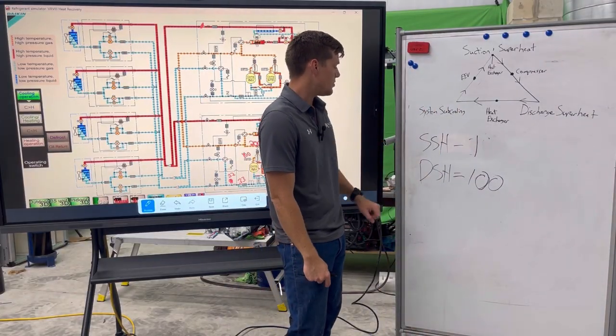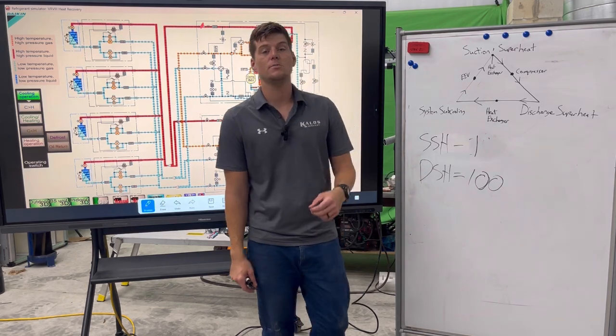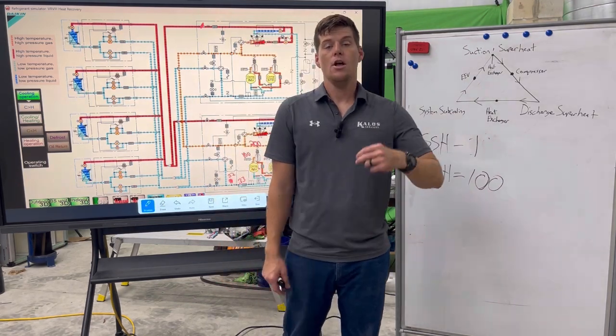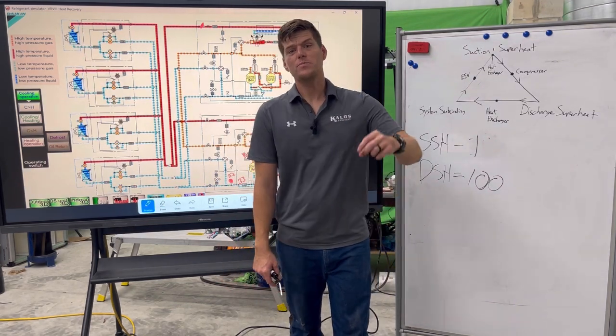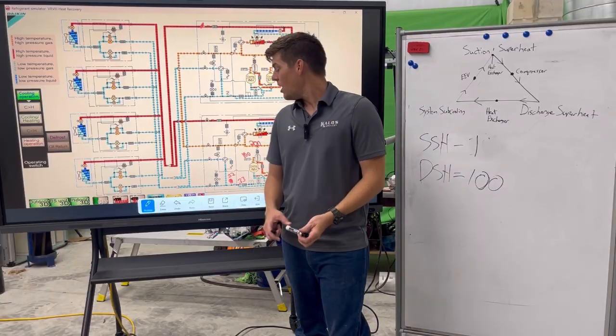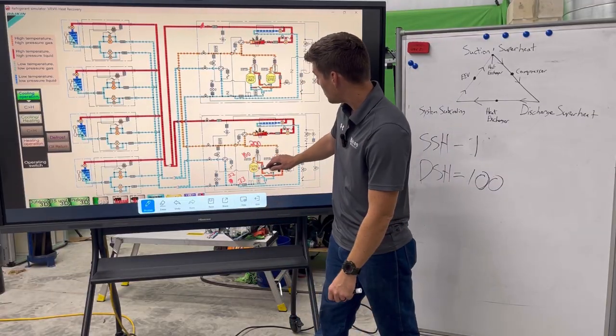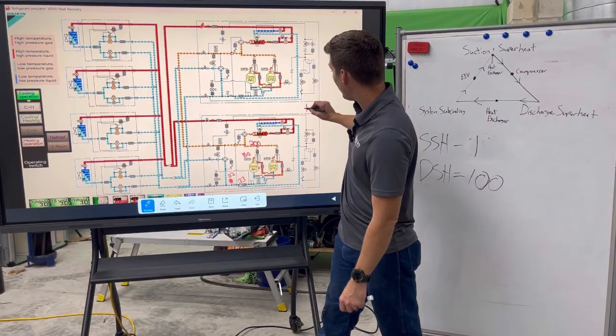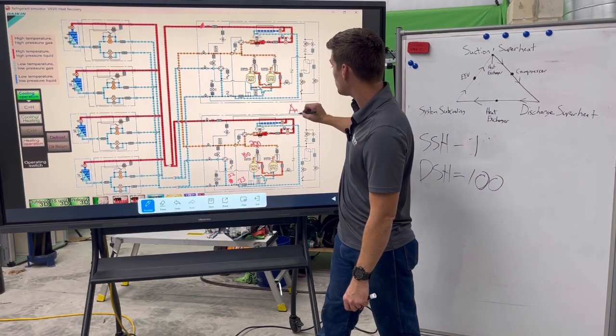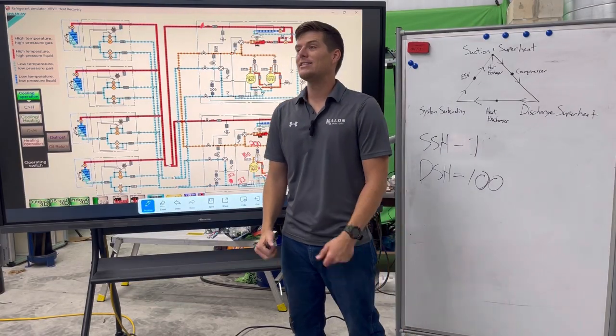Well, 1 degree suction superheat and 100 degree discharge superheat tells me there's damage to the compressor, there's no oil in the compressor. And what else am I going to look for here? I am going to look for, on my compressor, I'm going to look for elevated amps, right? Amp draw, right? There's going to be an excessive amount of load.